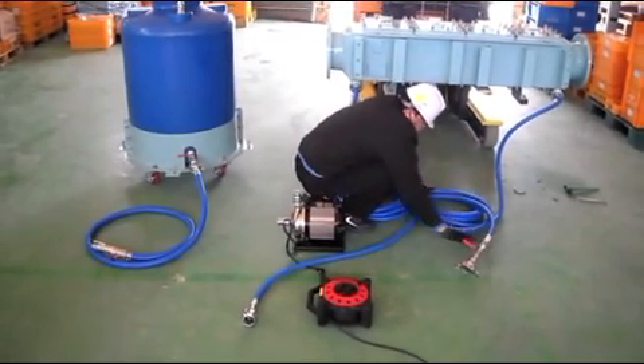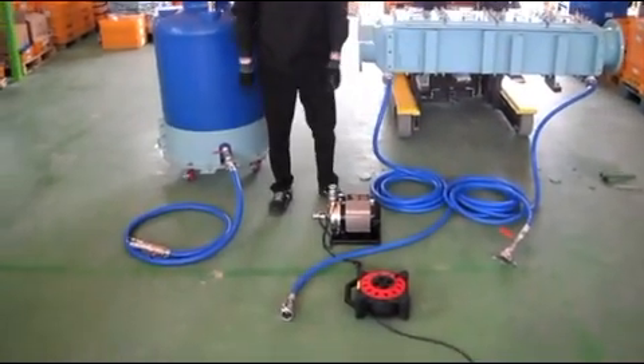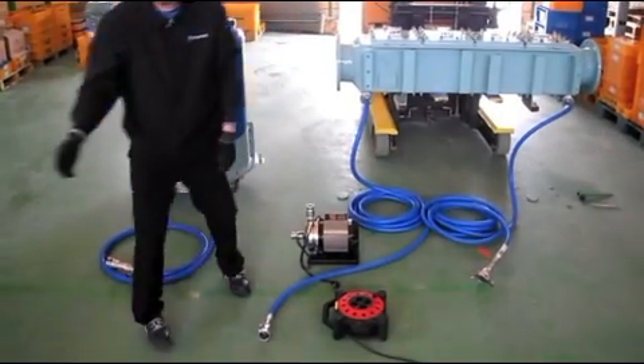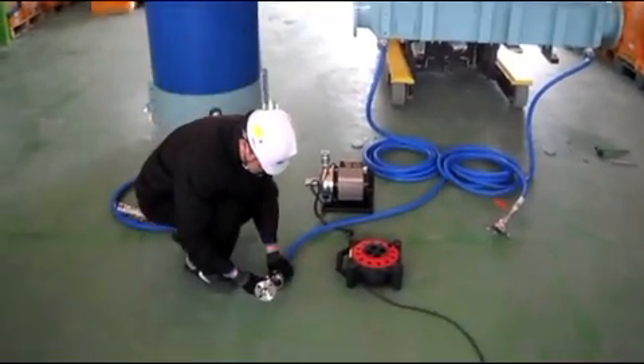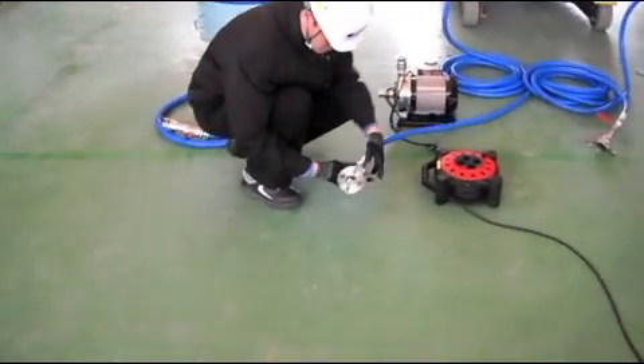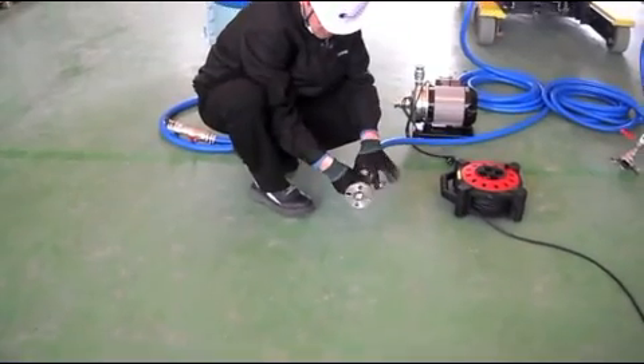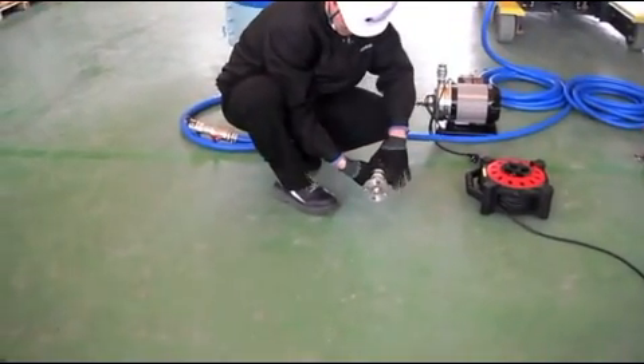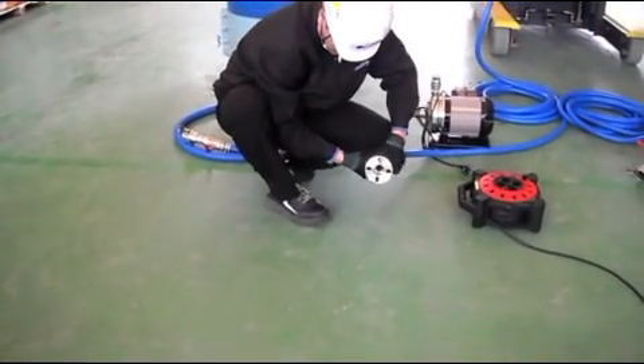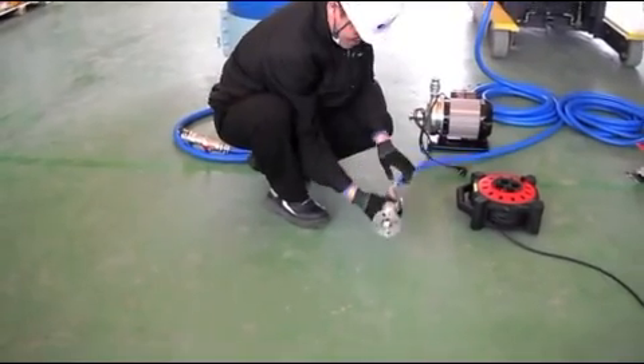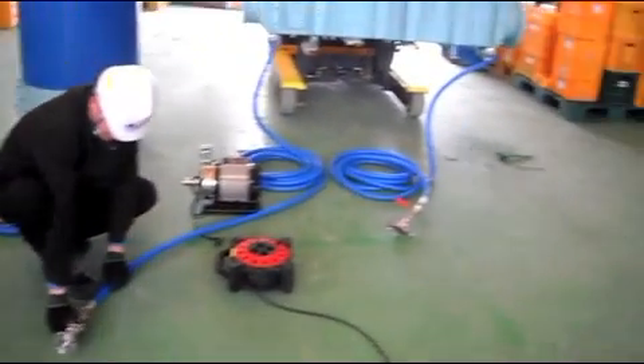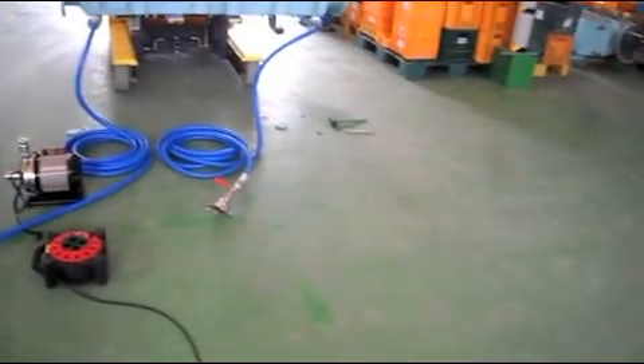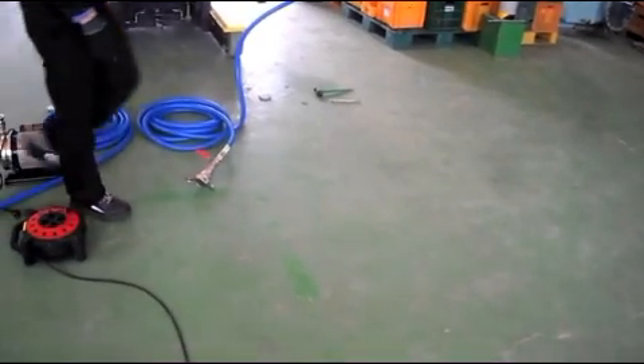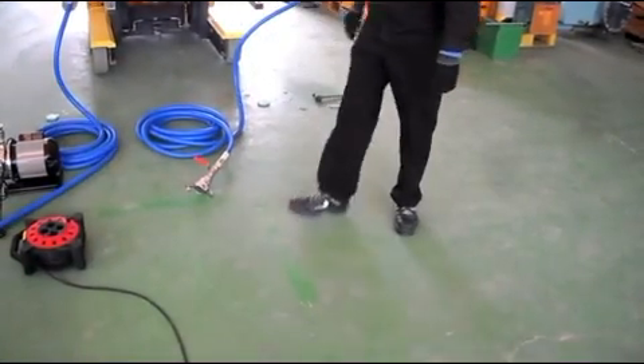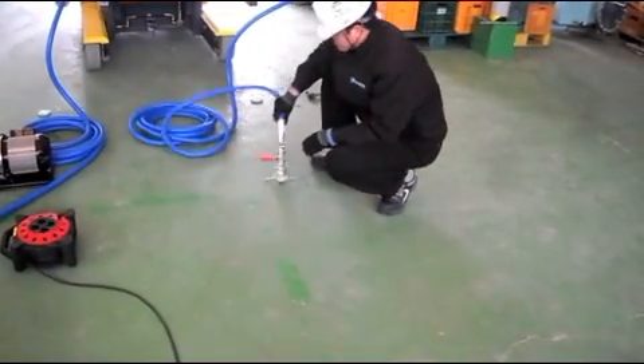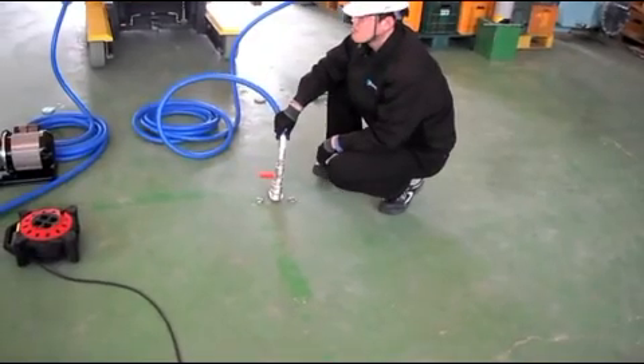3. Connect FW cooling service line of ship to coupling C4 of pipe C3 using connector. 4. Connect coupling C3 of pipe C2 to bilge holding tank pipe of ship using connector. Connector will be provided by the manufacturer. 5. Drain wastewater containing cleaning agent and open valves V3, V4 to clean inside of ECU.